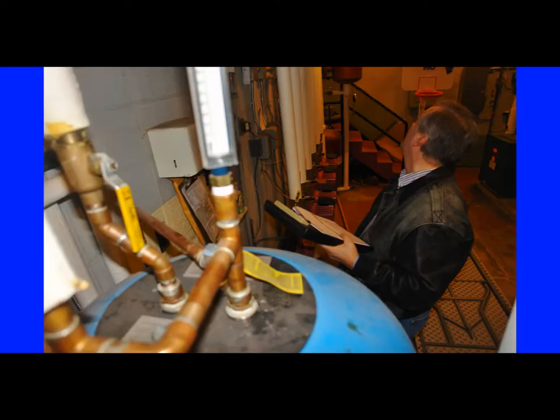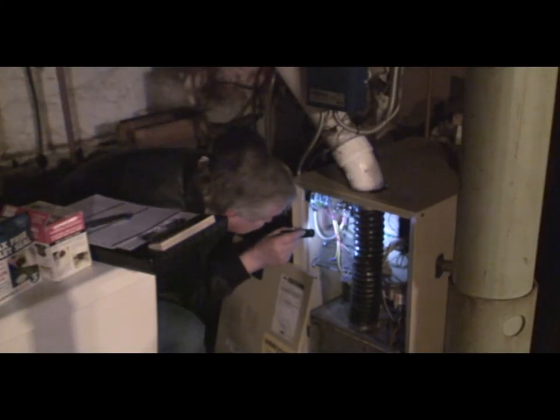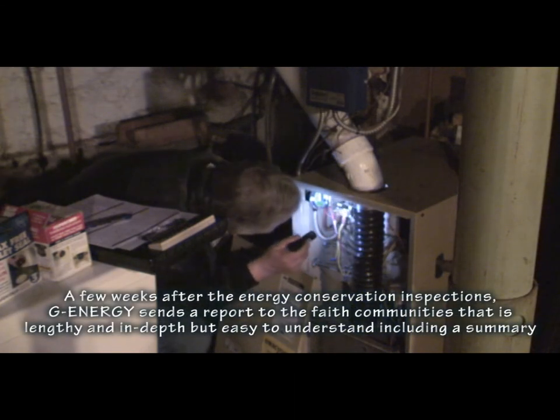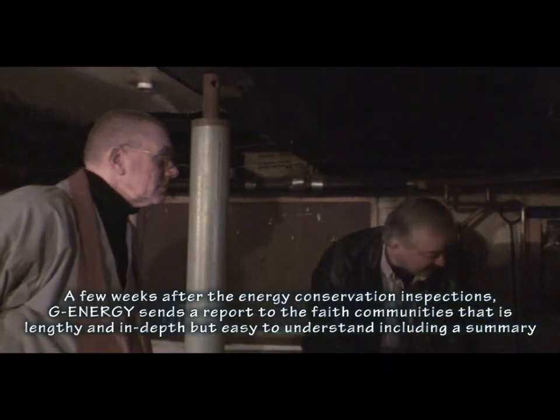They look newer, they're nice boilers, they're clean — can't be that old. Somewhere about 12, 13 years ago they were installed. The thermostat will try to combat it, and it'll be coming on and coming off, and it gets uncomfortable. What a reset control does is it senses the outdoor temperature and says, okay, it's 40 degrees out today, we only need the water to be 140 degrees, so it only allows the boiler to heat the water to that temperature. It saves energy in the long run and it pays for itself pretty quickly. I compare it to a clock thermostat — boiler reset controls pay for themselves quickly. They're a good device, and I don't see one on here.